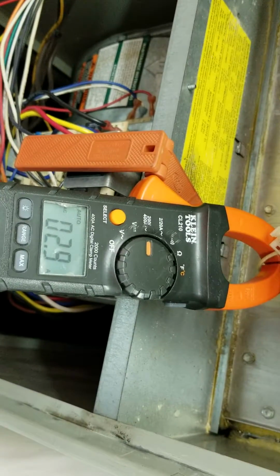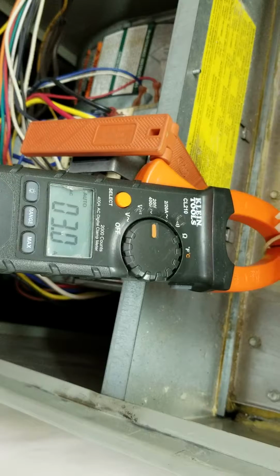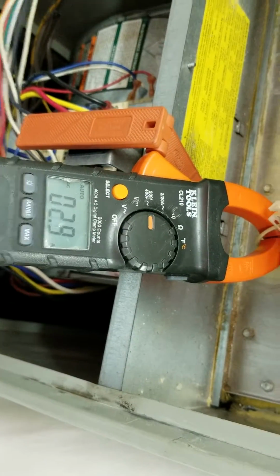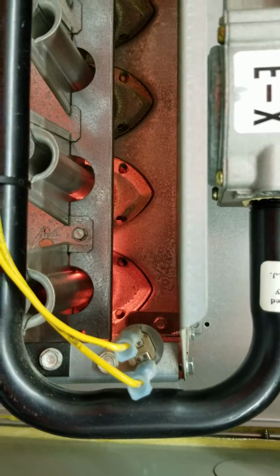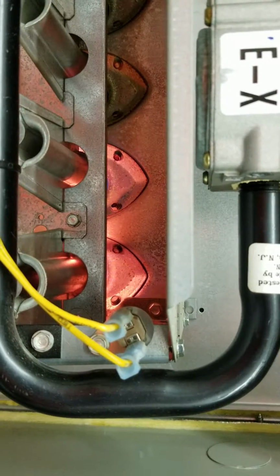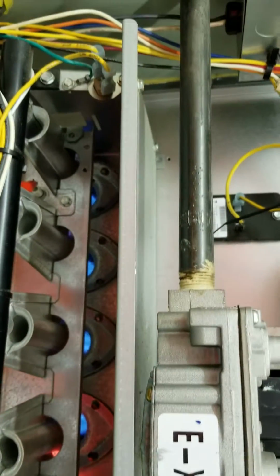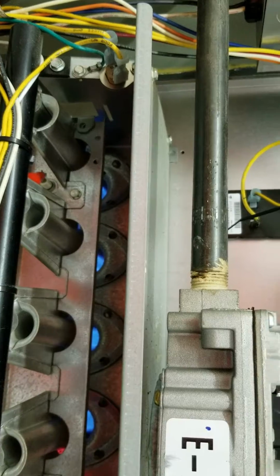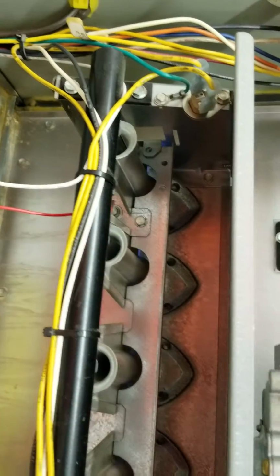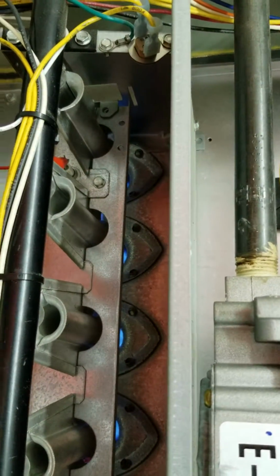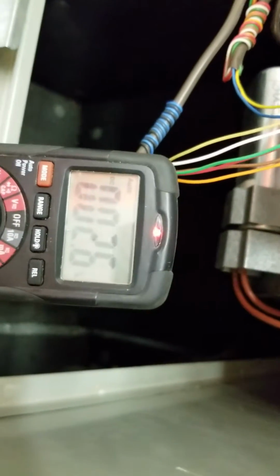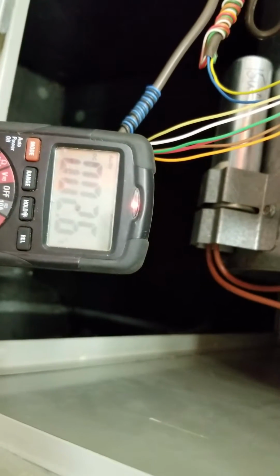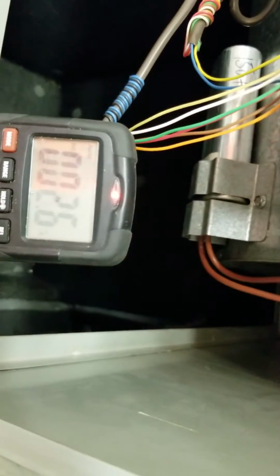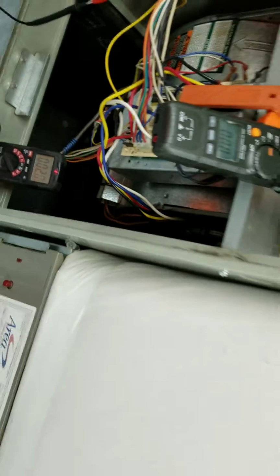And now we are at our hot surface igniter that is lighting up. You can see it there, it turns red. And the burners light all the way across. And now with the far left burner on, this is where the flame sensor rod is. Now we have 2.6 microamps of flame sensor current. This is the safety feature to this furnace.